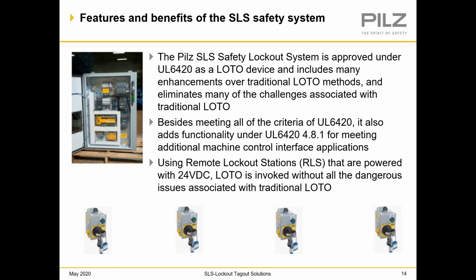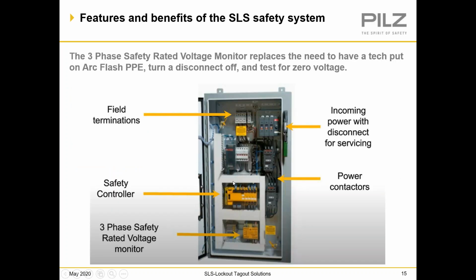Using remote lockout stations, RLS, that are powered with 24 volts, lockout is invoked without all of the dangerous issues associated with traditional lockout. For instance, here's 4 lockout stations that can be anywhere in the machine, controlling one source of energy. Here's the basic panel configuration. It has various functionality built inside.